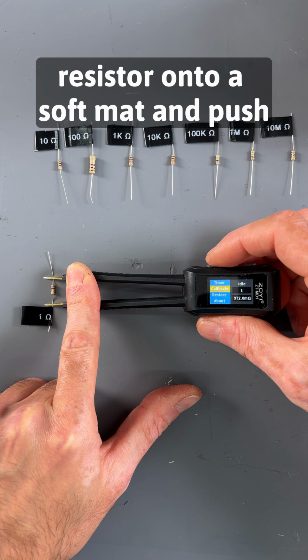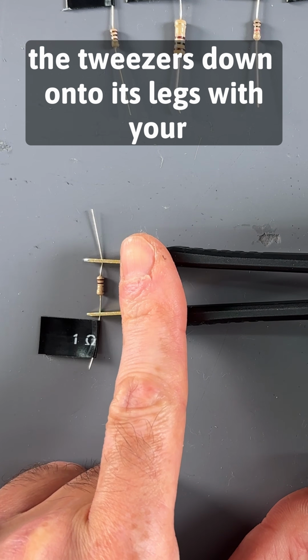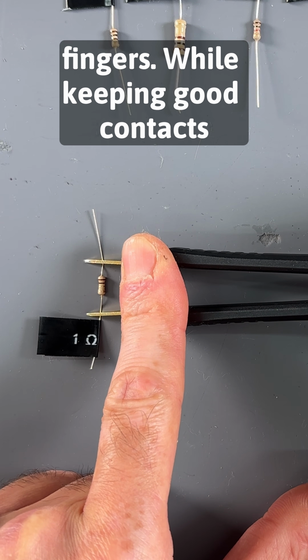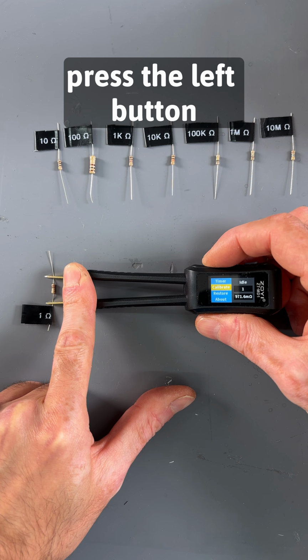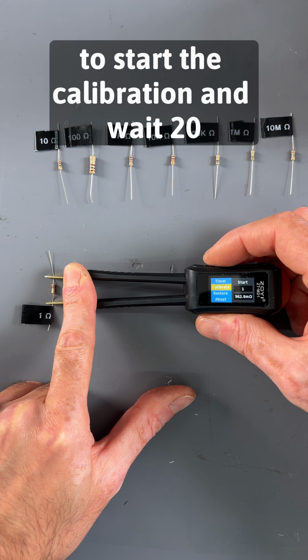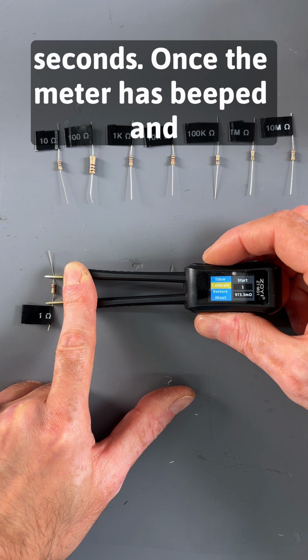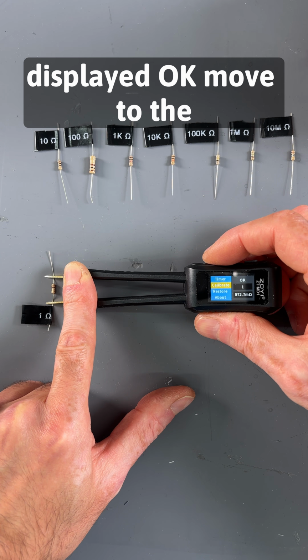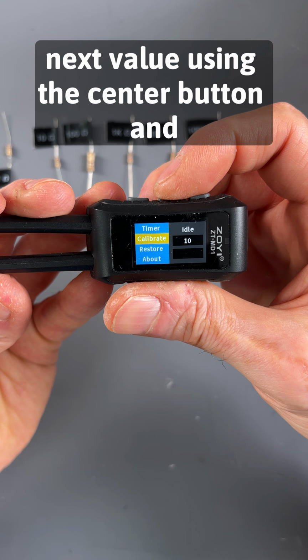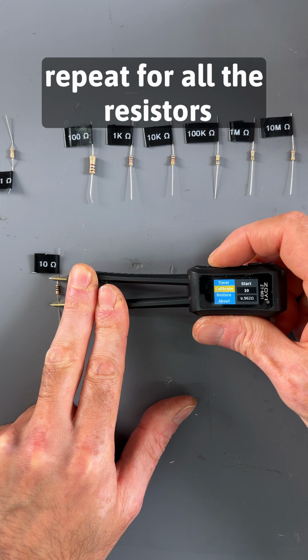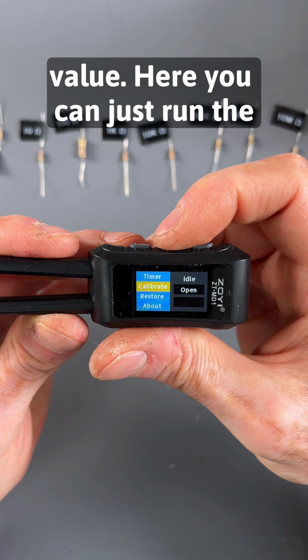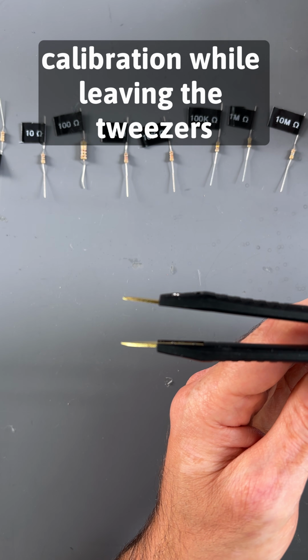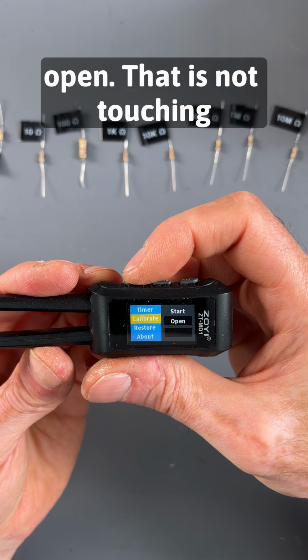Place the relevant resistor onto a soft mat and push the tweezers down onto its legs with your fingers. While keeping good contacts, press the left button to start the calibration and wait 20 seconds. Once the meter has beeped and displayed OK, move to the next value using the center button and repeat for all the resistors until you reach the open value. Here you can just run the calibration while leaving the tweezers open, that is, not touching anything.